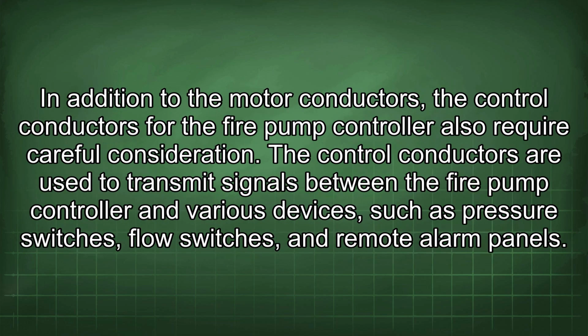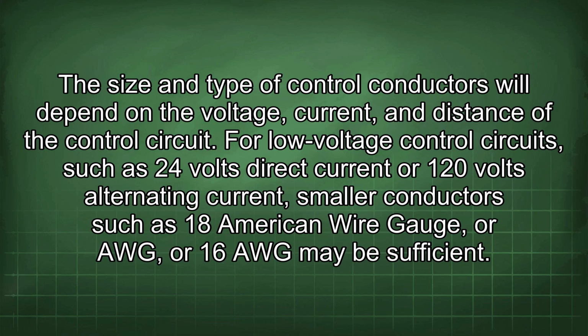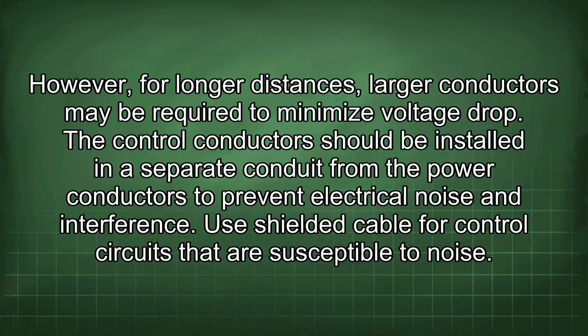event of a fire. In addition to the motor conductors, the control conductors for the fire pump controller also require careful consideration. The control conductors are used to transmit signals between the fire pump controller and various devices, such as pressure switches, flow switches, and remote alarm panels. The size and type of control conductors will depend on the voltage, current, and distance of the control circuit. For low voltage control circuits, such as 24 volts direct current or 120 volts alternating current, smaller conductors such as 18 American wire gauge or AWG or 16 AWG may be sufficient. However, for longer distances, larger conductors may be required to minimize voltage drop.